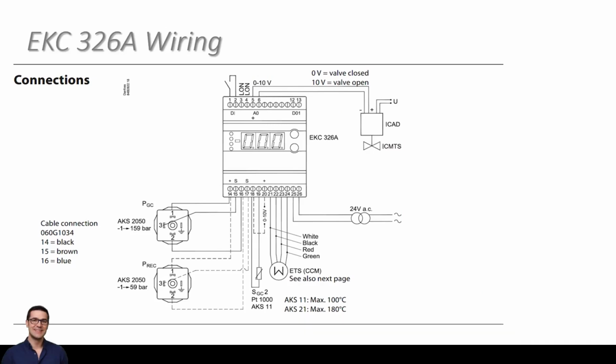Does a strap come in with that, or does a technician need to put that on? And what do you recommend? Because I know I've seen lots of it out there today, and I may have even done it, putting zip ties, which is the thing you cannot put on any temperature probe because they'll get brittle over time, they'll break. And I've seen that causing major issues, having that loose on the pipe. Is there anything that you guys recommend to tie it down with?